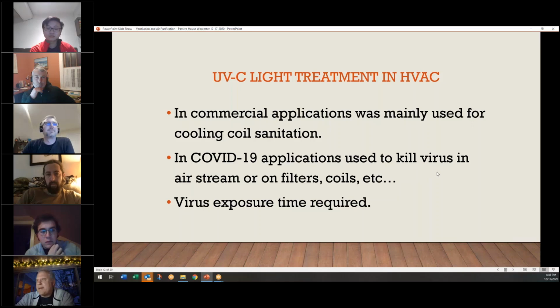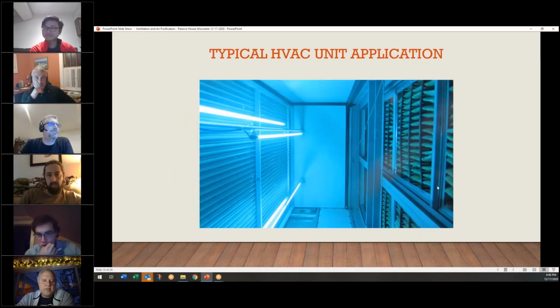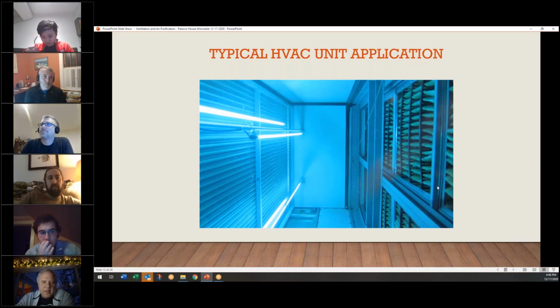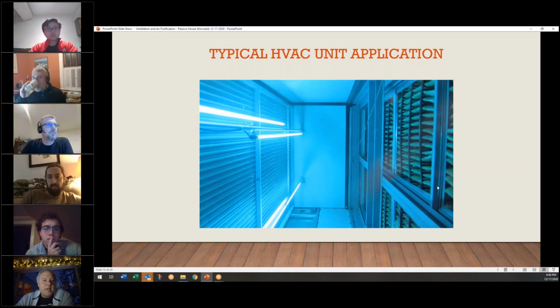Wes, if you want to go to the next slide, I think I should show a picture. Yeah. So there you go. You got the coil with the drain pan on the left, then you got the filters, and the air is coming from the right. Basically the lights are continuously exposing the coil, the downstream side of the filters, and the pan at the bottom to light, so it keeps any mold and slime buildup from going. That's how it would be put in a unit, and that's a good spot for it, because it's probably where the air is slowest in the unit, right at the coil. You're trying to slow things down. With the filters, you can't really go much higher than 350 to 500 feet per minute. So that's the spot where you want to keep the air the slowest.